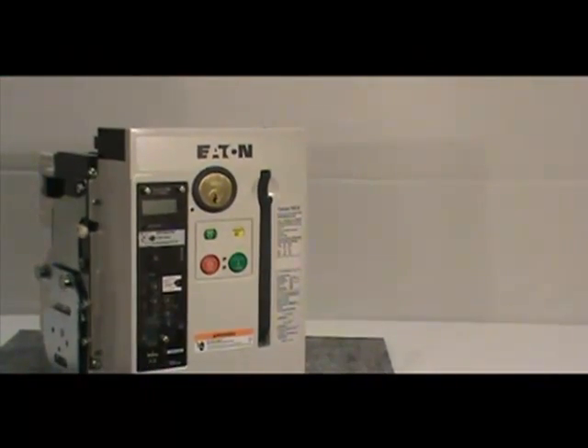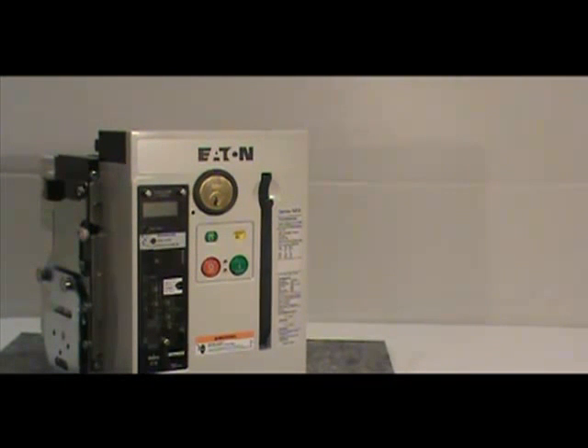Once the breaker is charged, try to push the green button, push to close, the breaker should not close.